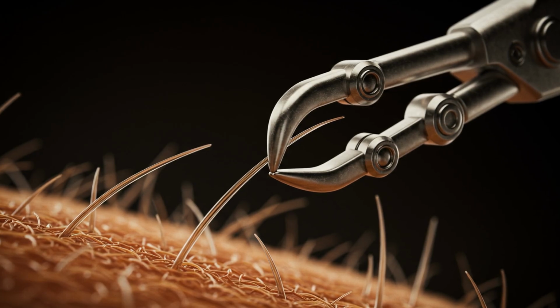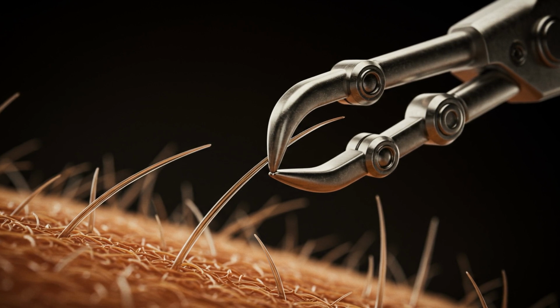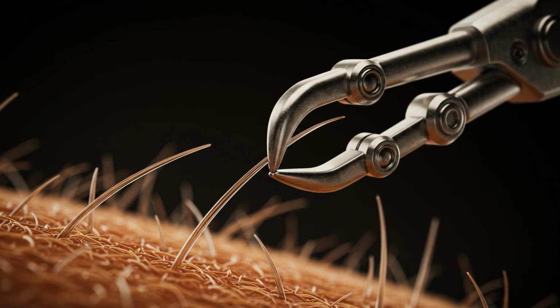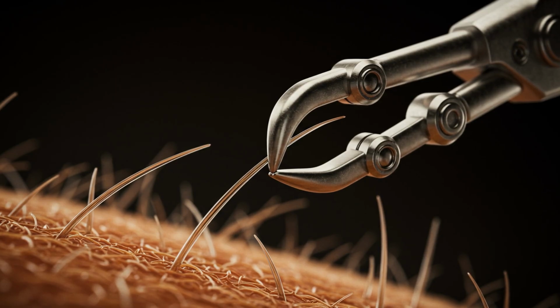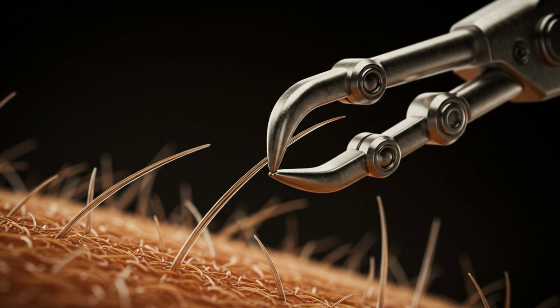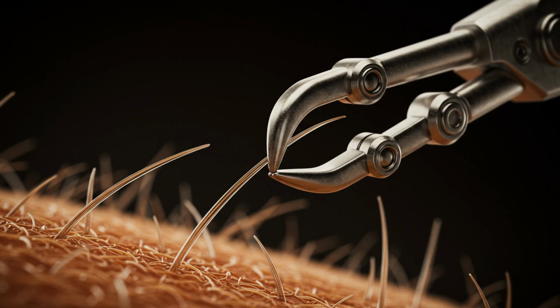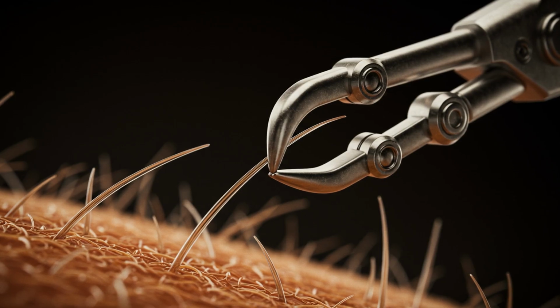These are masterpieces of micro-manufacturing. Some are so small they can fit through a hole the size of a pencil eraser. Each instrument has its own miniature cable drive system and wrist that provides 7 degrees of freedom. The manufacturing of these tools involves laser welding, micro-electrical discharge machining, EDM, and assembly under high-power microscopes. Because these tools are used to cut and cauterize, they must be made of specialized alloys like martensitic stainless steel, which can hold a razor-sharp edge while remaining resistant to corrosion.